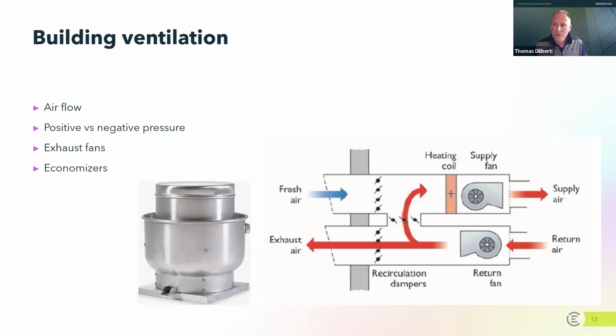The best example of this is during shoulder seasons. Many times there's an opportunity to get free cooling by using fresh air that's cool outside and pulling it into the building. So rather than turning on a chiller or air conditioning system to make cold air, you open the dampers to allow more fresh air in to help keep the building cool. That's the concept of economizers: taking advantage of the right kind of air outside—not too hot, not too cold, not too humid—so you don't have to heat or cool it. You're trying to get an economy, to save on the cost of heating and cooling the air, because you already have good quality air outside.